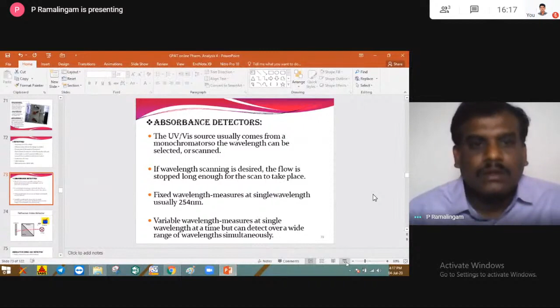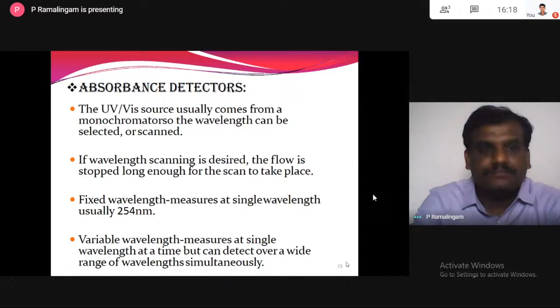So next, according to that, we come to the absorbance detector. The more commonly used absorbance detector is the UV visible detector, and it is based on monochromatic light of a wavelength which is passed through a sample, or rather through the eluate, and based on the absorbance you are able to get a chromatogram. In the case of absorbance detectors, there is a fixed wavelength detector which measures your eluate only at 254 nanometer. There is another detector called a variable wavelength detector, which measures the sample at different points of your UV visible region simultaneously.